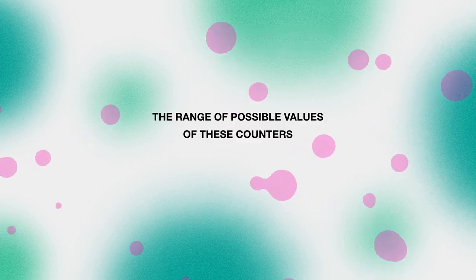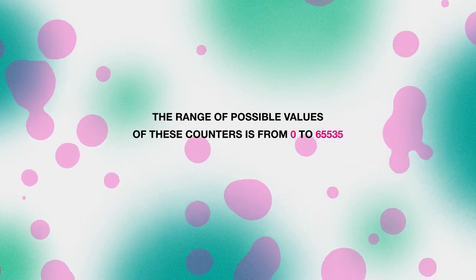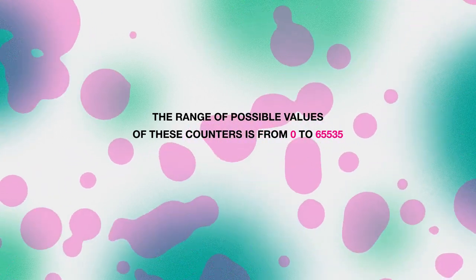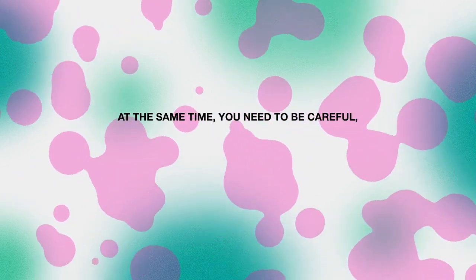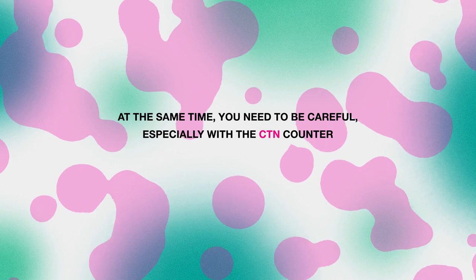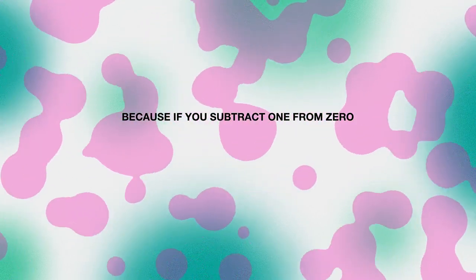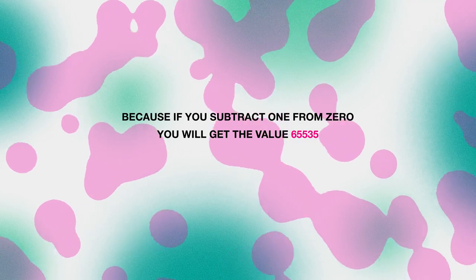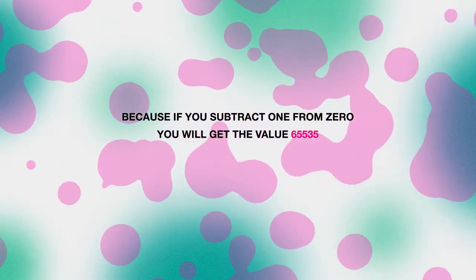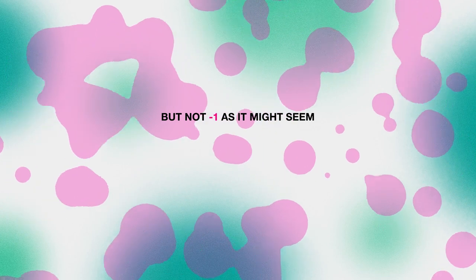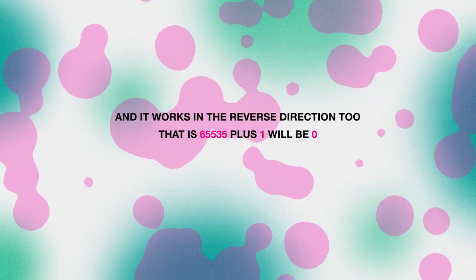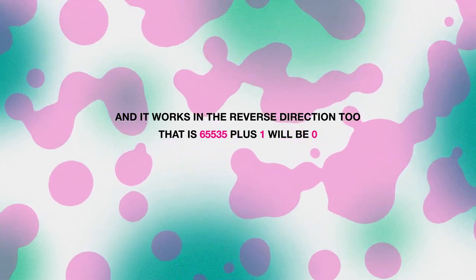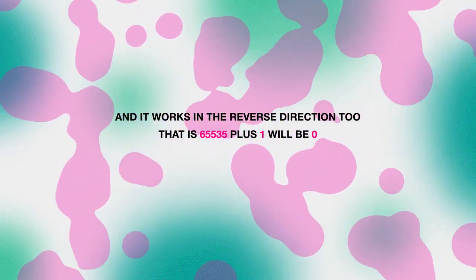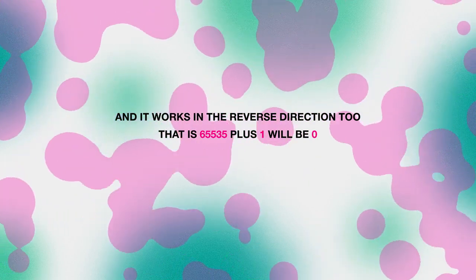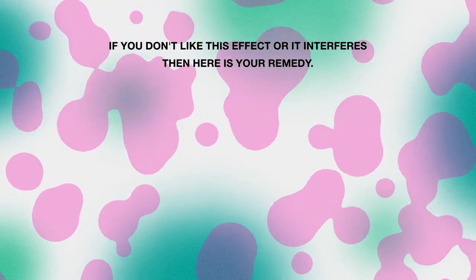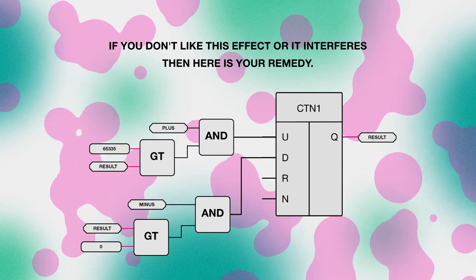The range of possible values of these counters is from 0 to 65,535. At the same time, you need to be careful, especially with the CTN counter, because if you subtract 1 from 0, you will get the value 65,535, but not minus 1, as you might have expected. This effect is called overflow, and it works in the reverse direction too, that is 65,535 plus 1 will be 0. If you don't like this effect or it interferes, then here is your remedy.